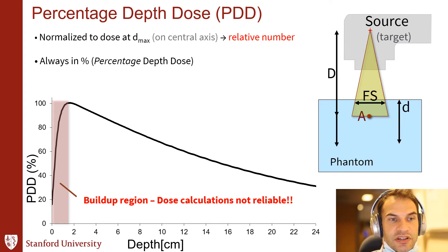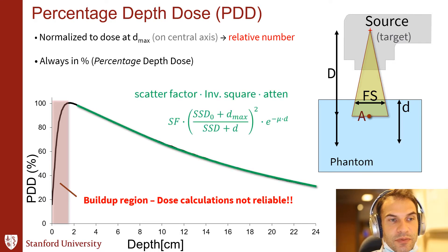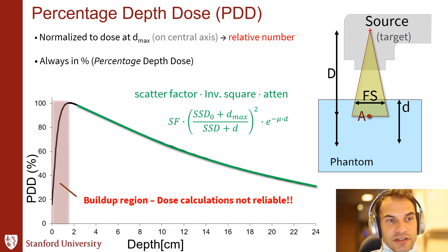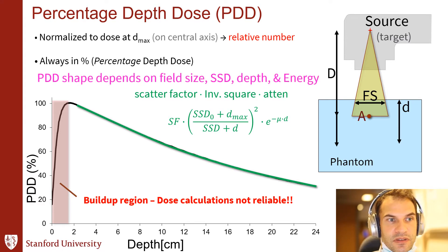There's a build-up region where dose calculations are not reliable. It's due to two reasons: the steepness of the curve there and also the variability of that part of the curve due to varying amounts of contamination from the head of the linac. The curve past the depth of maximum dose is more reliable, but it's a combination of an inverse square function, an exponential decay as a function of depth, and some scatter factors. The PDD shape depends on field size, SSD, depth, and energy.